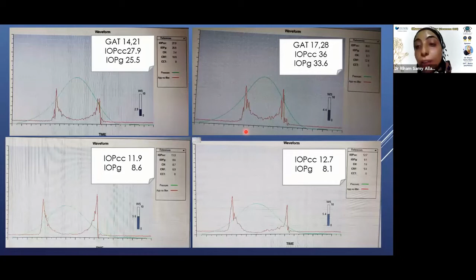So, to summarize, the sources of error in GAT can be related to the technique, the area and duration of contact of the applanation tip, fluorescein and illumination, and something which I did not mention, which is the magnification. You have to be sure that you are set on a magnification of ×1 or ×10, because sometimes some residents fall into the mistake of putting it on high magnification and failing to get a proper intraocular pressure. For the cornea, an important target for applanation, you should take into consideration abnormalities in shape, presence of astigmatism, structure and thickness.